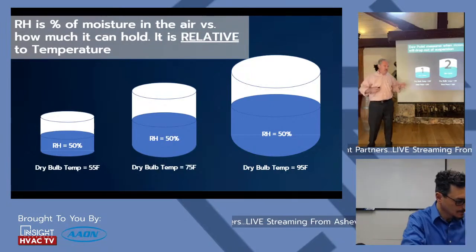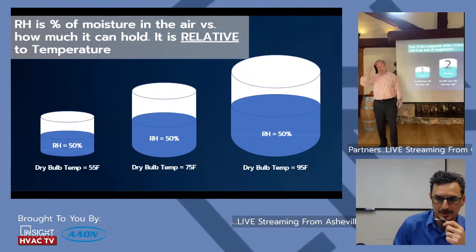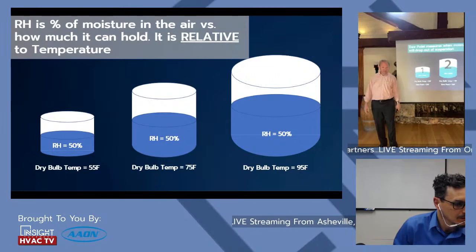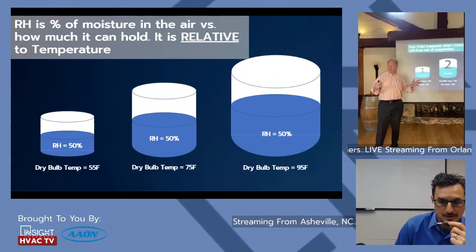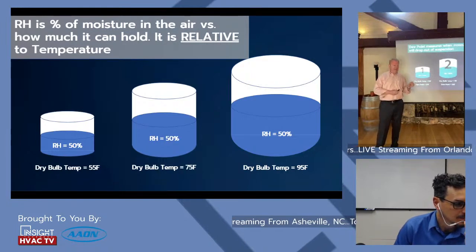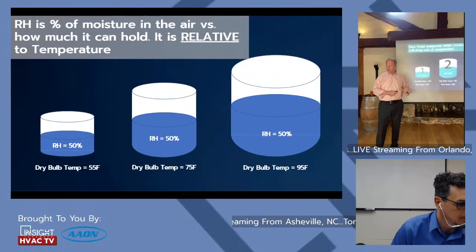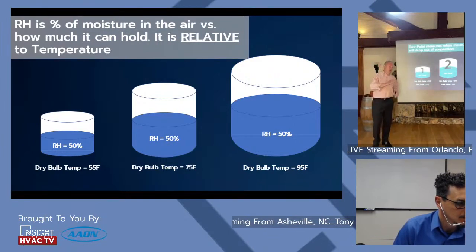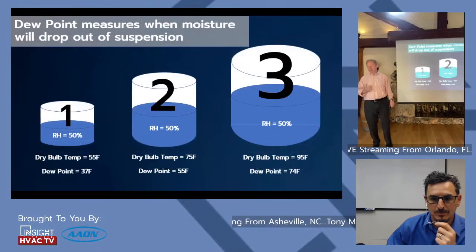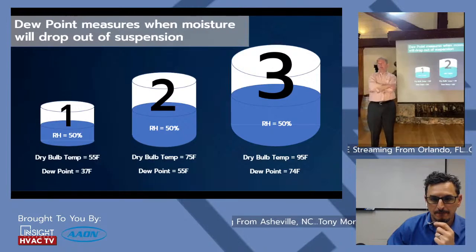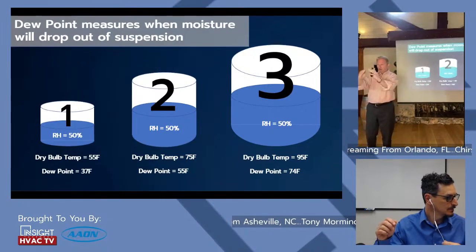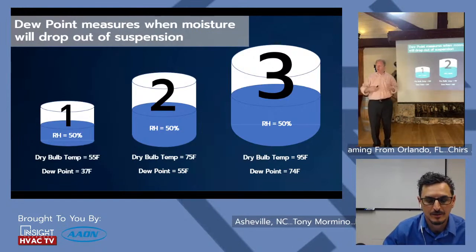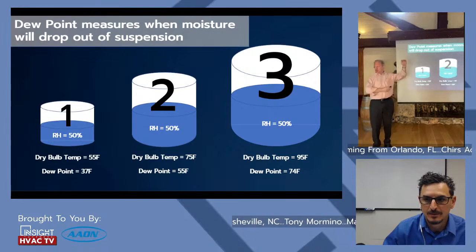Here in Florida, we hear people say 95 degrees at 90% relative humidity — no, it's not. 90 degrees at 90% RH is something like 200-plus grams of moisture. The highest design load I've found is 189 grams in Venezuela. So you're not going to hit 90-90 in normal conditions. I did have one person tell me it does happen — and it does, in the Persian Gulf between a couple of rivers — but at 90-90 the design temperature was 125°F, so it only happens briefly.